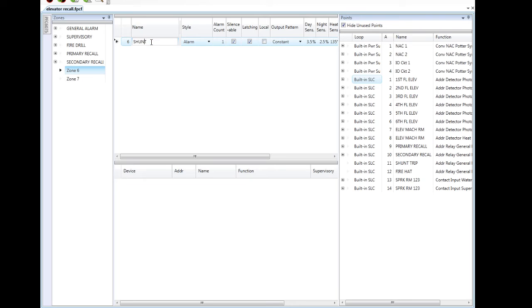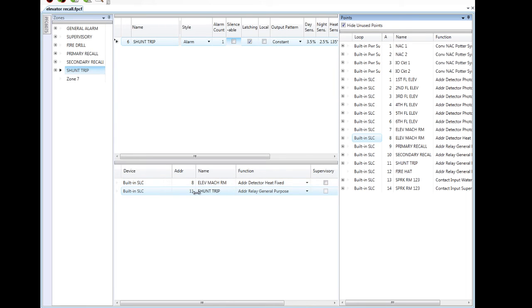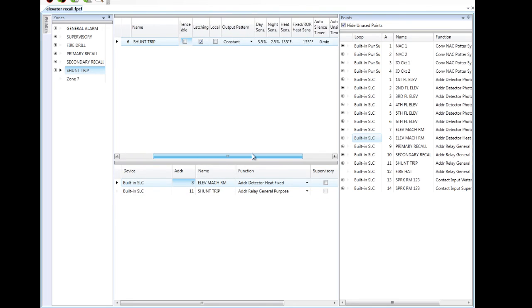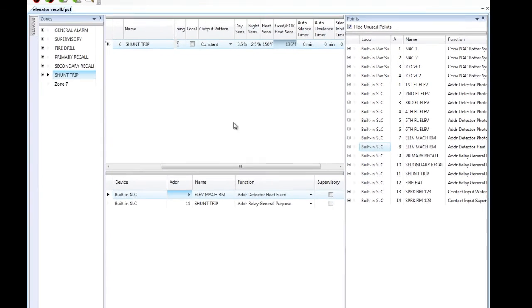My next zone is going to be shunt trip. I'm going to make this non-silenceable. I'm going to grab the output, which is the relay for shunt trip. This particular relay is going to be triggered by the heat detector in the elevator machine room. In the event that the heat detector is active, we know that at some point in the near future the sprinkler is going to potentially open up and dump water into this room. So we want to trigger this relay indicating that they need to kill power to the elevator controls prior to the sprinkler head opening up. I also need to make sure that this fixed heat detector's alarm threshold is less than the sprinkler head. It is currently set to the default of 135 degrees Fahrenheit. I'm actually going to change that to 150 degrees for the alarm threshold.